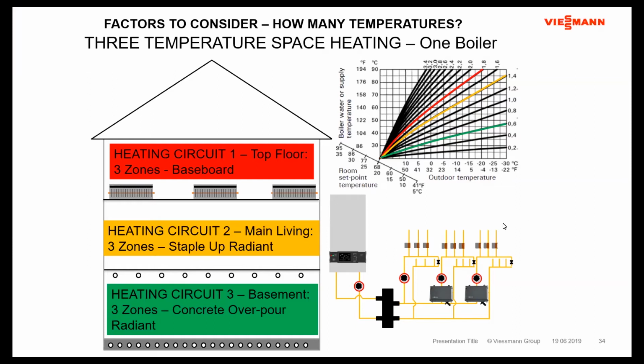In comparison to doing this with thermostatic mixing valves, so pulling these off and just throwing thermostatic mixing valves in, the big difference is these are going to be about 5 to 6% more efficient on average per year than a thermostatic mixing valve would be in the exact same application. Thermostatic mixing valves don't do anything other than put a ceiling, just cap the max temperature going out to these zones. They don't actually adjust and manipulate the supply temperature when it's in a lower temperature capability.